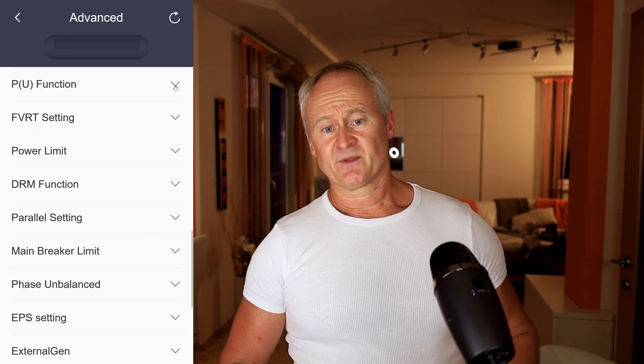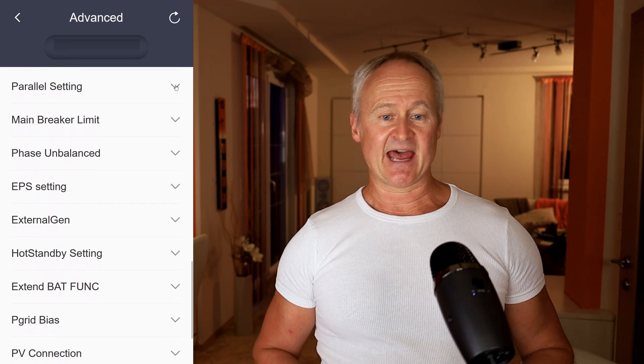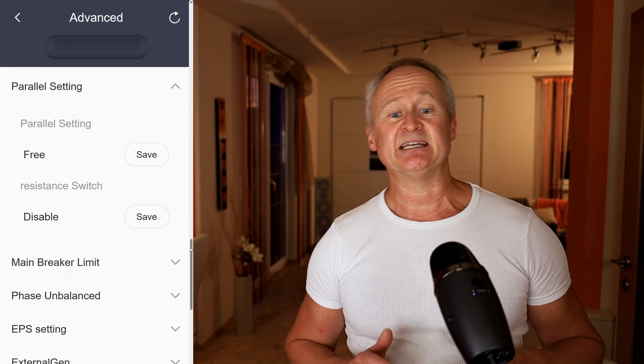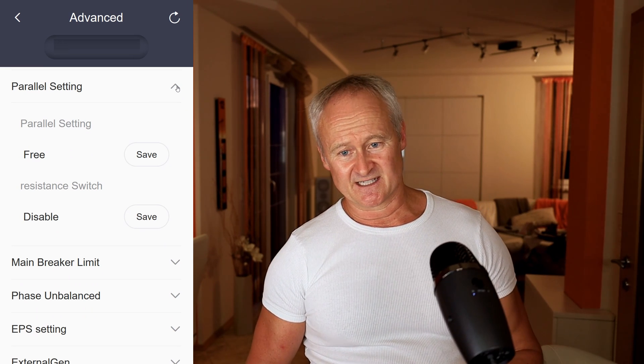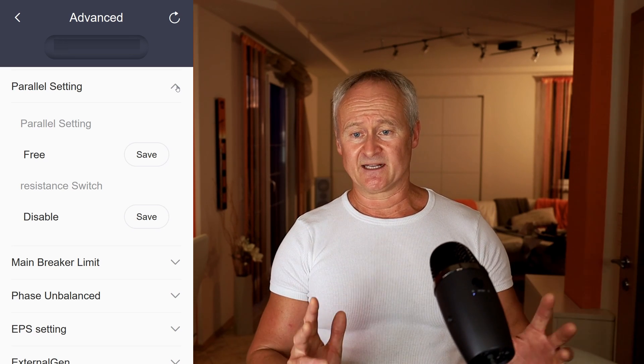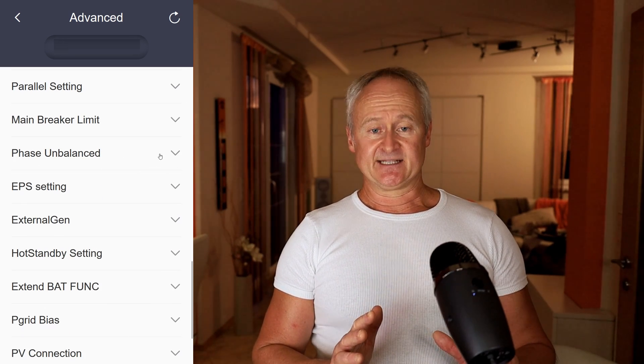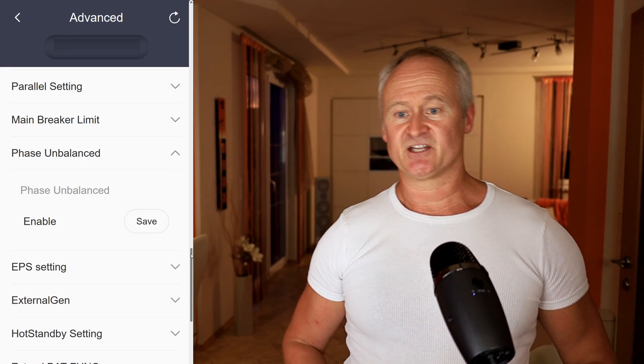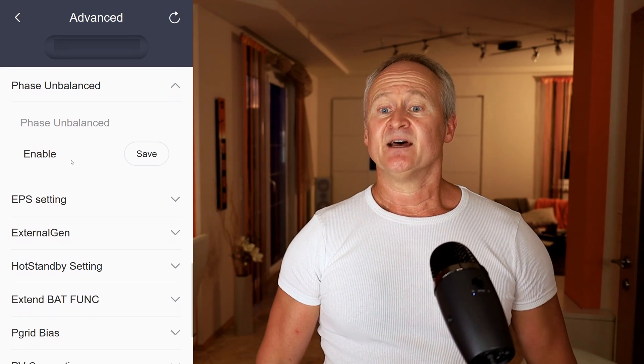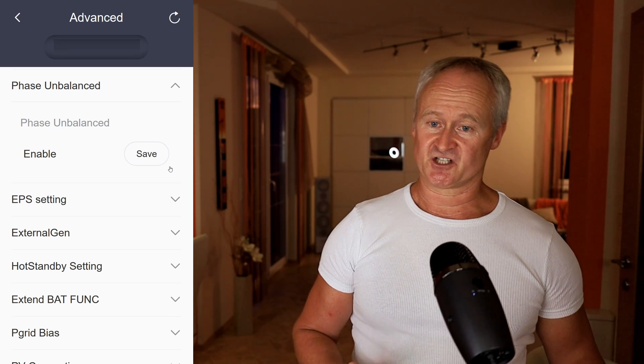The next function is Parallel Settings. You should know that you can connect up to 10 Solax X3 Hybrid Inverters in parallel. The advantage of this is that all devices are involved in EPS mode. However, there are many things to consider and numerous parameters to set up in a parallel installation, which can be found under this menu item. Phase Unbalanced is a function that allows the inverter to distribute the generated energy not only symmetrically but also asymmetrically across the three phases. The inverter is highly capable of handling unbalanced loads and this function can be advantageous in grid operation.